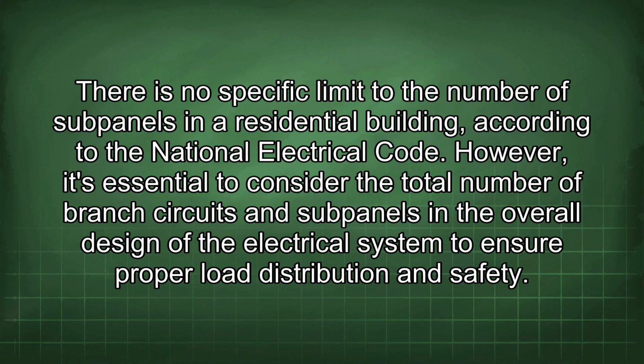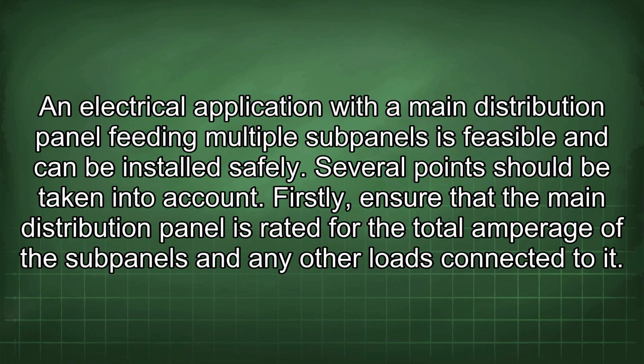There is no specific limit to the number of subpanels in a residential building according to the National Electrical Code. However, it's essential to consider the total number of branch circuits and subpanels in the overall design of the electrical system to ensure proper load distribution and safety. An electrical application with a main distribution panel feeding multiple subpanels is feasible and can be installed safely.